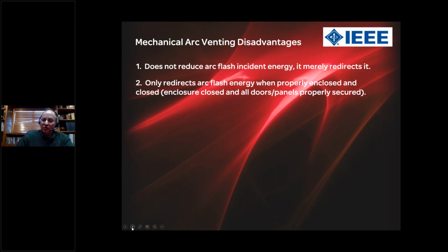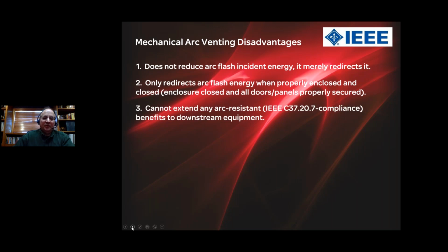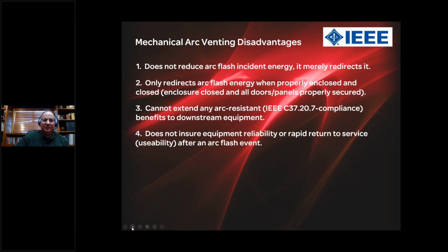Just as electricity follows all paths but favors low impedance paths, in an arc flash event, the plasma favors low air pressure paths. So if you open a panel on arc resistant mechanically vented gear, the arc flash event, if it does occur, is coming right to you. Number three, you cannot extend any arc resistant benefits to downstream equipment, which is the subject of this presentation. We intend to extend those benefits to drives and motor control centers and panel boards and other type tested equipment. It does not ensure equipment reliability or rapid return to service. Again, the focus is strictly on person safety, not venting out the front, back, rear, or low voltage compartments in the equipment.